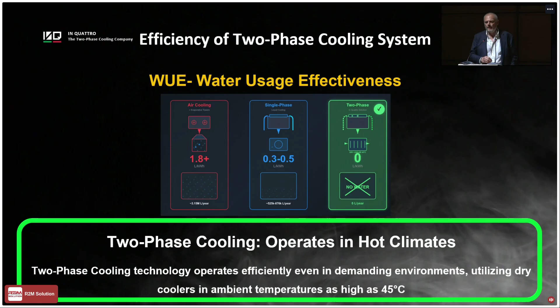So, again, what are other advantages of two-phase cooling solutions? It's possible to simplify the infrastructure of a data center. Here there is a very schematic representation of a data center with two racks in this case. And so you see that the heat is transported outside the data center and released to the ambient with the dry cooler. The dry cooler, as already explained, is a device that, without using water, can release heat outside, even at higher ambient temperatures, like 45 or 50 Celsius degrees.